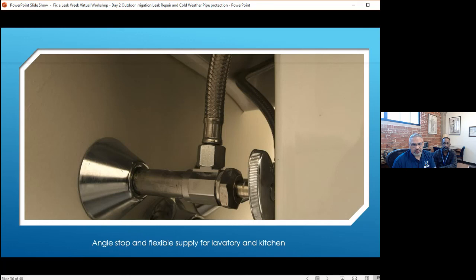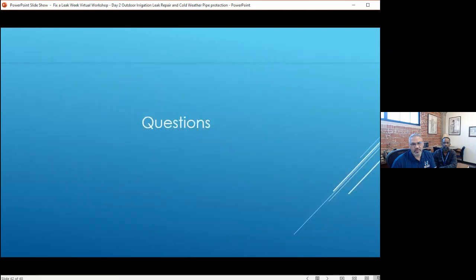You still have to, because the pressure vacuum breaker, like I said, has a critical level, and it'll be marked with a CL. Typically, it's kind of etched into the valve itself. So from that line, 12 inches below, you're not supposed to have any of those sprinkler heads come up to that level. So if you're increasing the height of your shrub sprayers, you may want to also consider raising the level of your backflow preventer. In the city of Houston, we use the pressure vacuum breakers. I know earlier there was a double check that was shown in the ground, and those we have a little different requirement here.